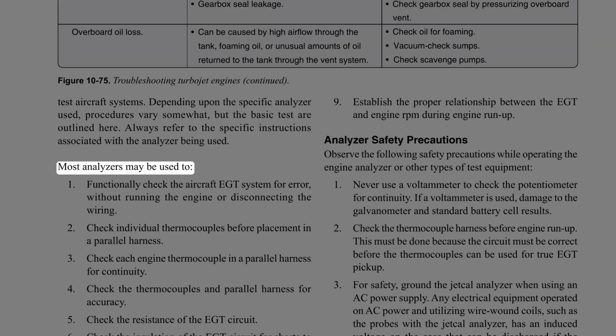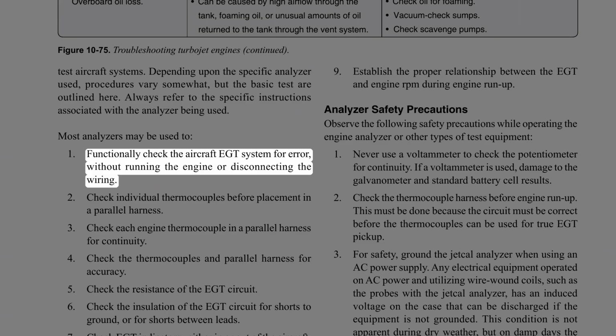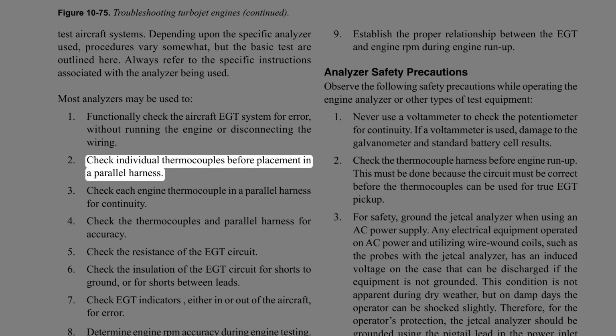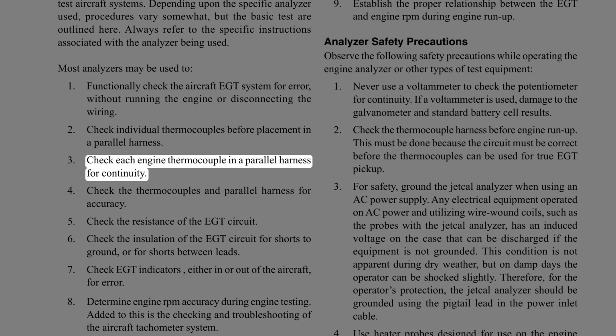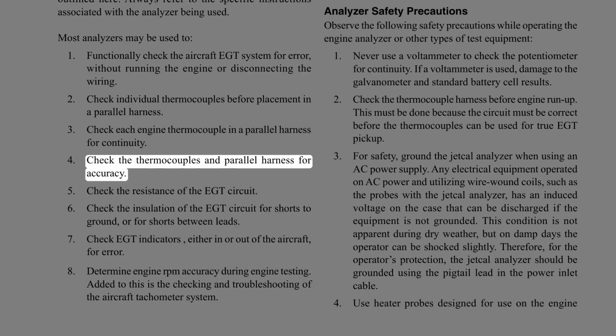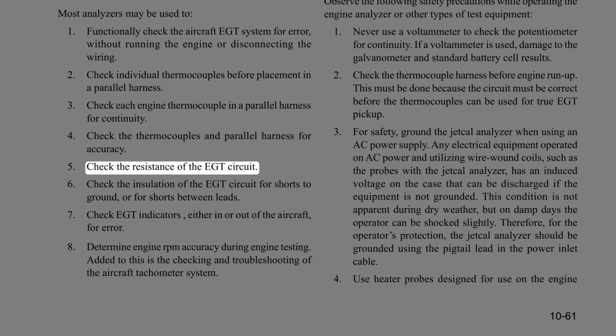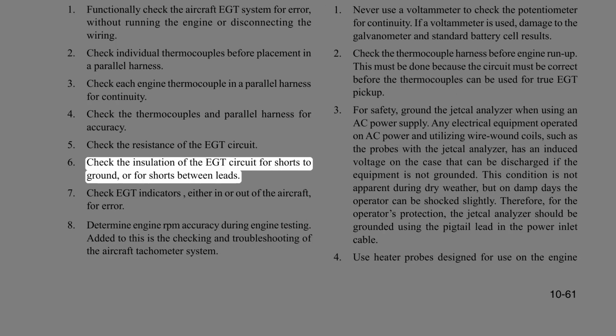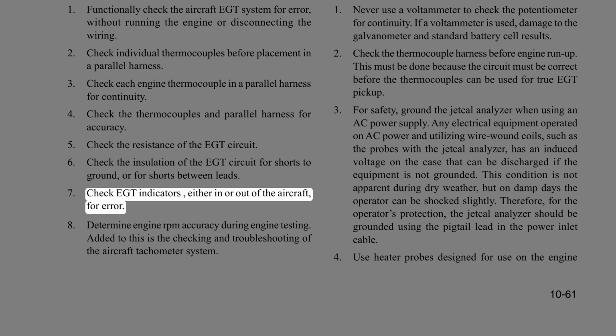Most analyzers may be used to functionally check the aircraft EGT system for error, without running the engine or disconnecting the wiring. Check individual thermocouples before placement in a parallel harness. Check each engine thermocouple in a parallel harness for continuity. Check the thermocouples and parallel harness for accuracy. Check the resistance of the EGT circuit. Check the insulation of the EGT circuit for shorts to ground, or for shorts between leads. Check EGT indicators, either in or out of the aircraft, for error.